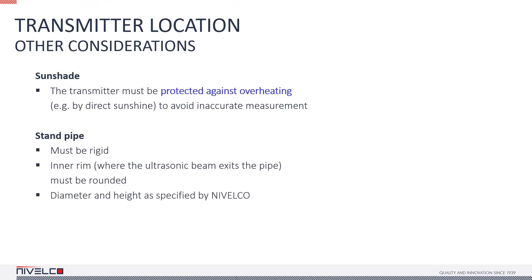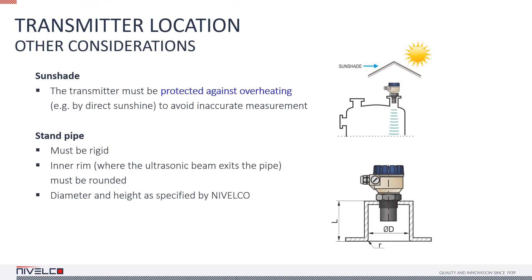The use of standpipes is generally unfavorable. If, however, it becomes necessary to use one, they must comply with the dimensional and geometrical requirements to avoid problems in measurement. The pipe's diameter must be at least the size specified for the particular device, and the inside of the pipe must be rounded to avoid any echoes reflecting from its surface.